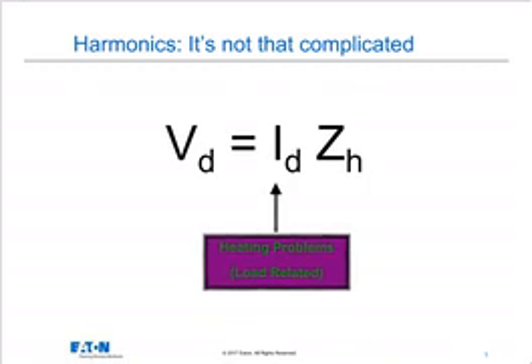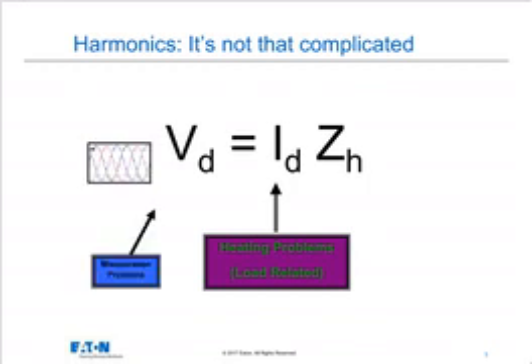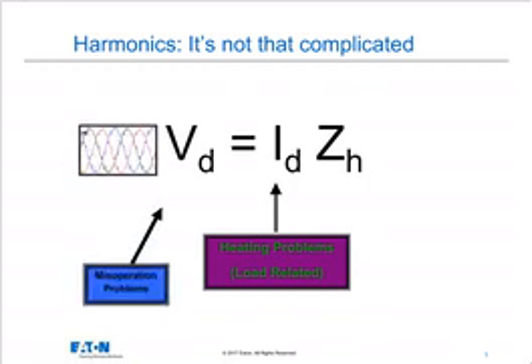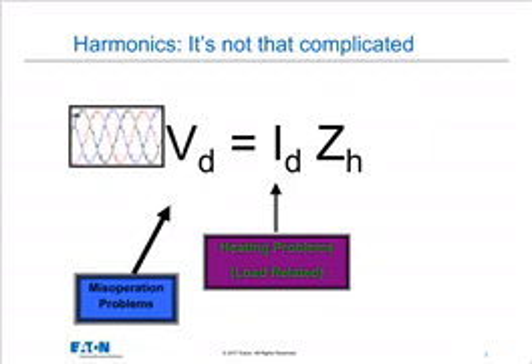So as I add another UPS, another drive, another harmonic source, my voltage distortion grows. And with voltage distortion, the second problem comes in. So the first problem is heating, and the second problem is misoperation. You have things that don't operate properly when the voltage becomes more and more distorted.